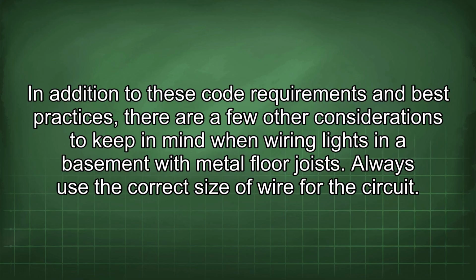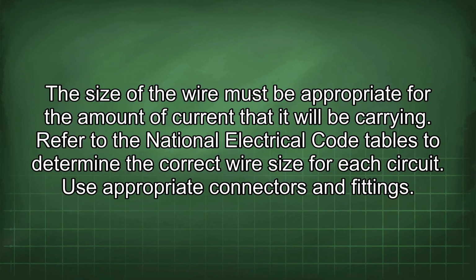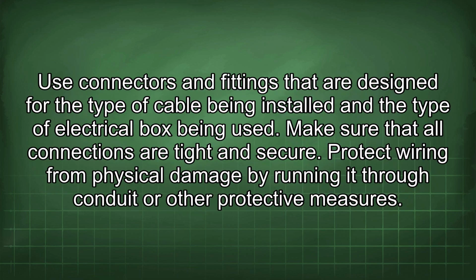Always use the correct size of wire for the circuit. The size of the wire must be appropriate for the amount of current that it will be carrying. Refer to the National Electrical Code tables to determine the correct wire size for each circuit. Use appropriate connectors and fittings. Use connectors and fittings that are designed for the type of cable being installed and the type of electrical box being used. Make sure that all connections are tight and secure.